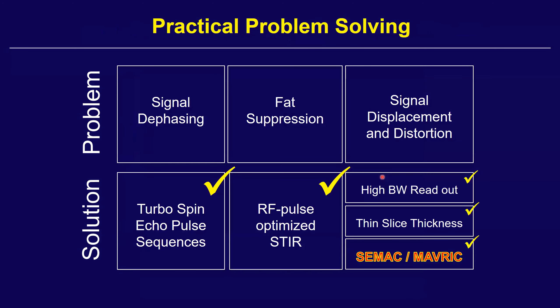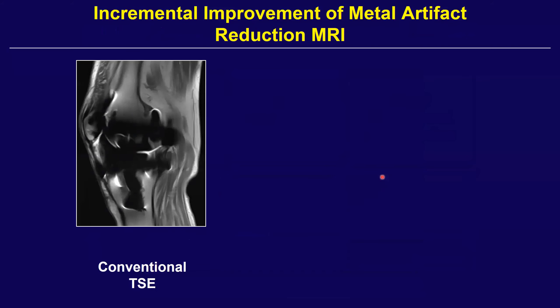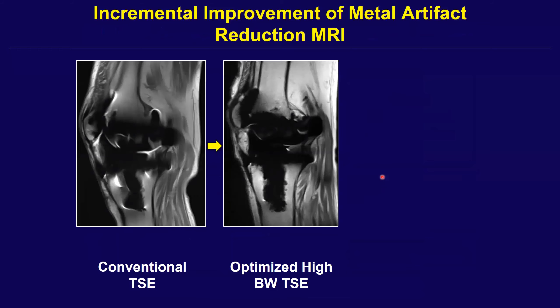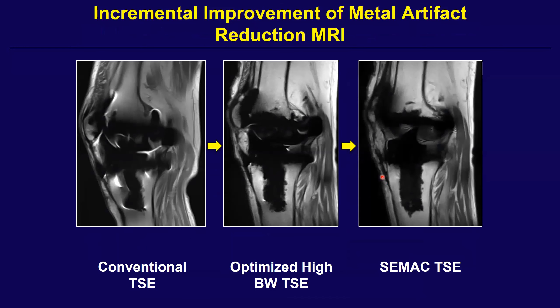Applying advanced metal suppression reduces through-plane signal displacement in the slice encoding direction — the dimension otherwise missed with high bandwidth alone. Following the evolution: from conventional TSE, to optimized high bandwidth TSE, to adding SEMAC algorithms on top — which also uses VAT — all of a sudden you can see the joint space, pseudo-capsule, fluid between components, tibial component, and part of the tibial tray. You can also see the bone-implant interface to better advantage.